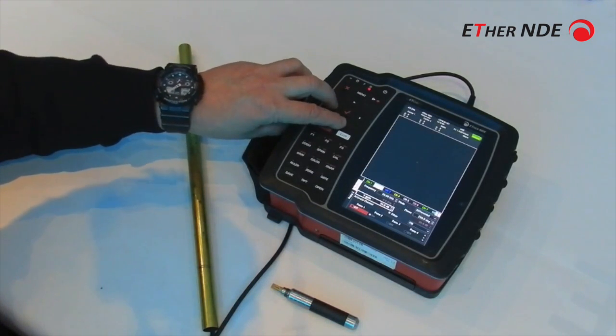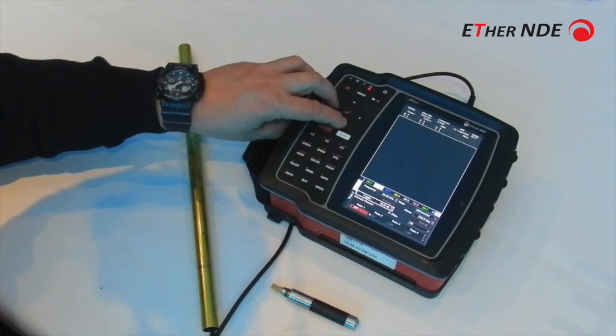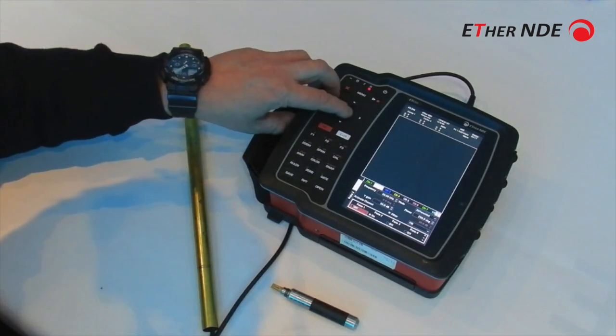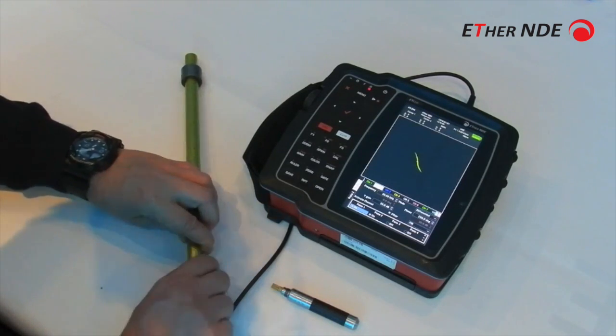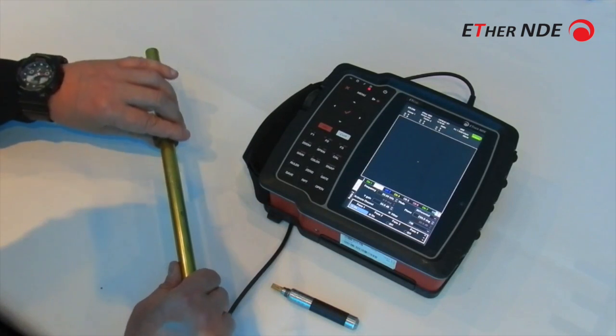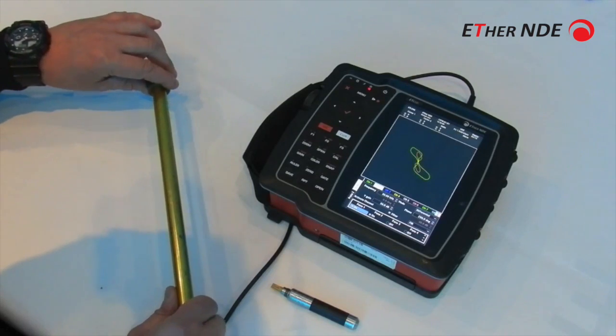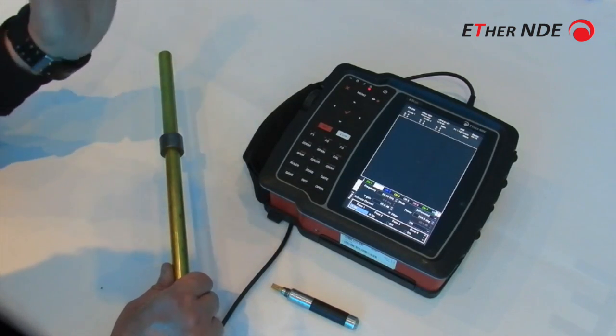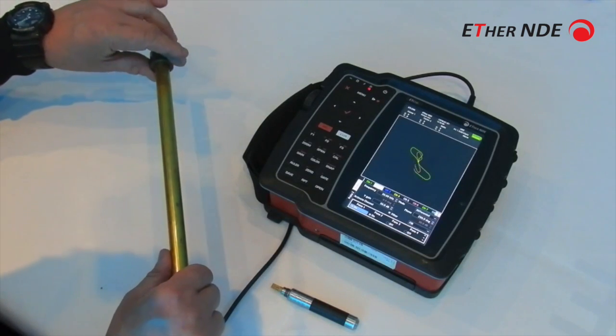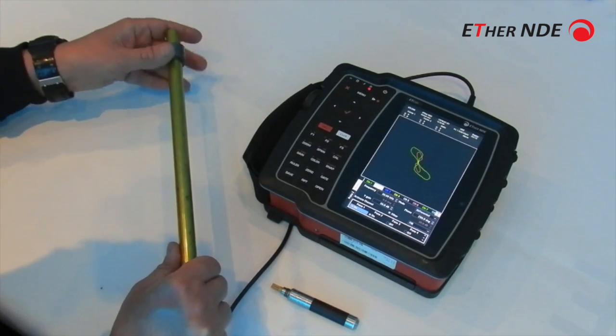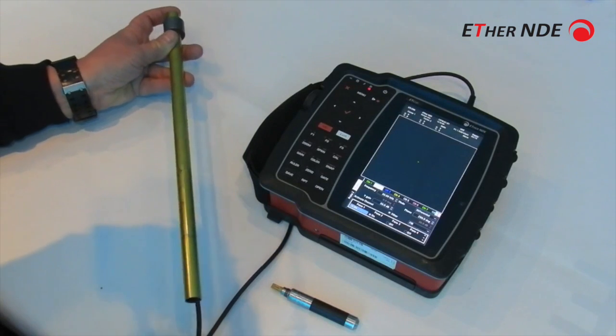If I go down here and display the channel, I can have two traces. This is the two support plate signals. I'll get slightly diminished signal and phase shifted at the higher frequency of 30 kilohertz and the 20 kilohertz.